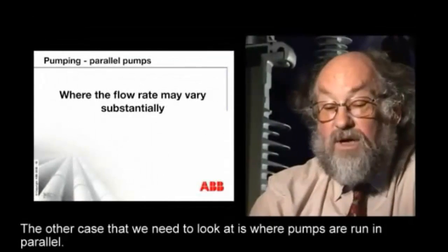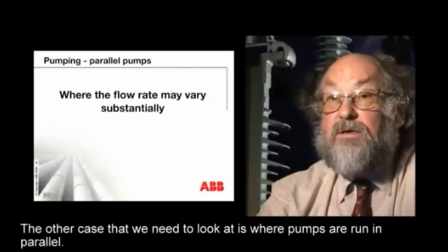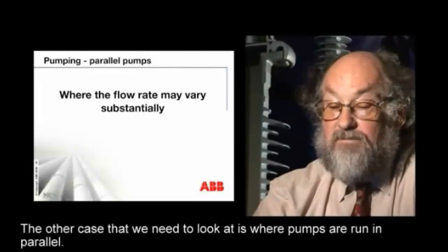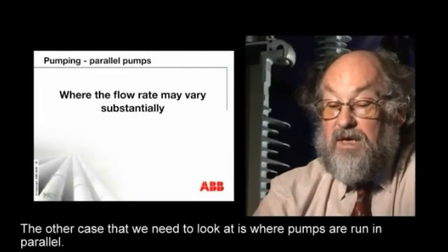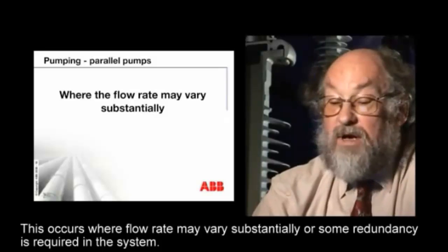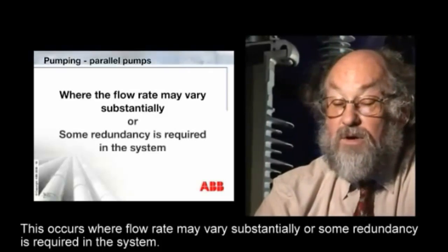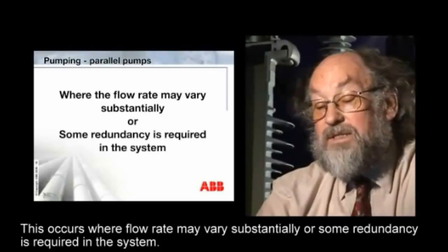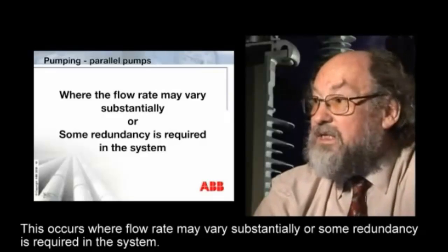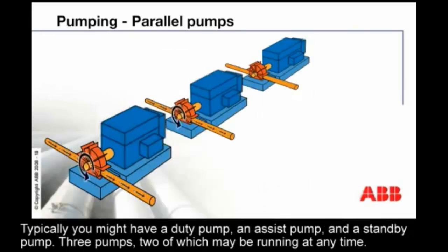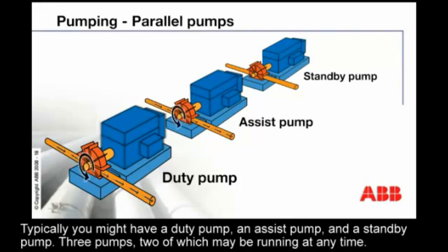The other case that we need to look at is where pumps are running parallel. This occurs where flow rate may vary substantially or some redundancy is required in the system. Typically you might have a duty pump, an assist pump, and a standby pump — three pumps, two of which may be running at any time.